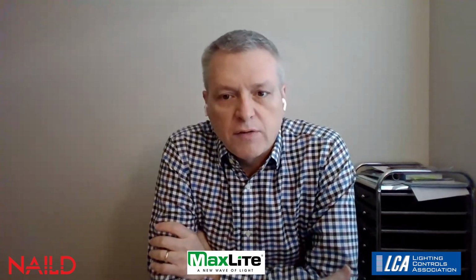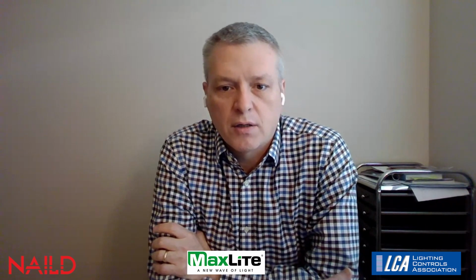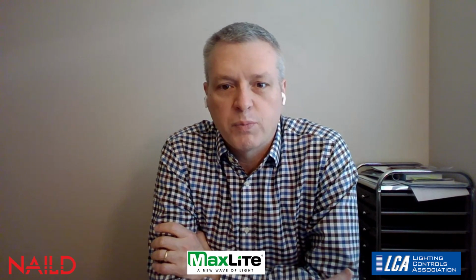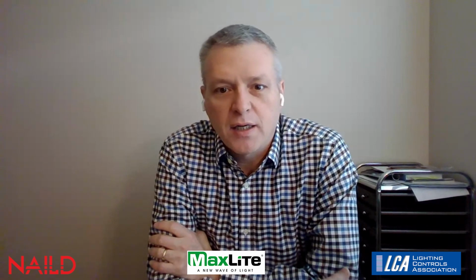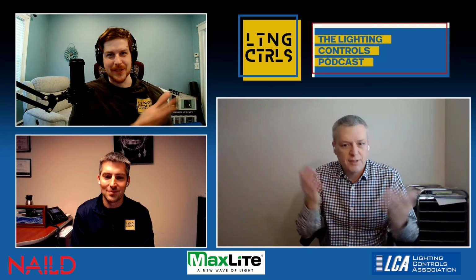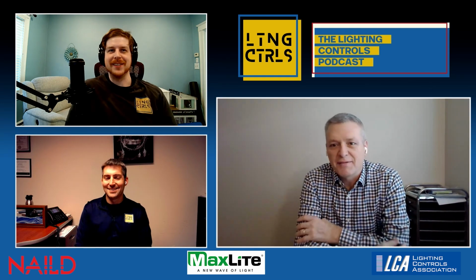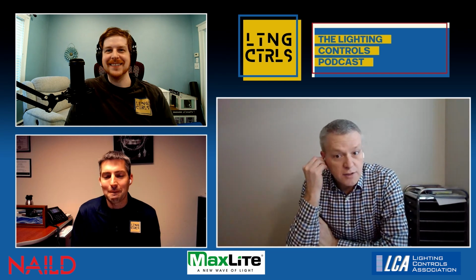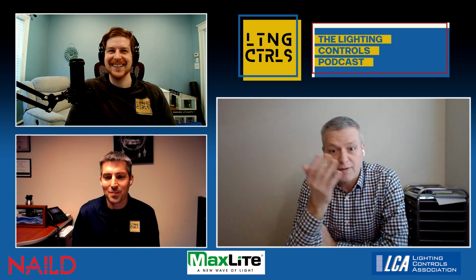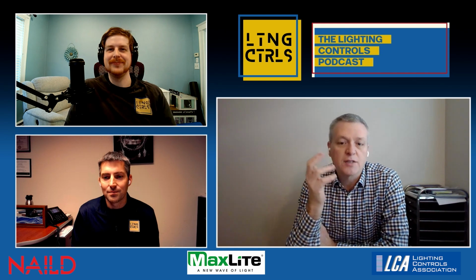We had one installed at the luminaire level, and the fixture was right behind a hanging projector, with the heat vent from the projector blowing right onto the sensor. You wouldn't think about it. It was a pendant mount fixture, and the sensor was literally 2 inches from where the heat was blowing out of the projector for the classroom. Because it had passive infrared, it was seeing that air movement as movement and triggering all the time.